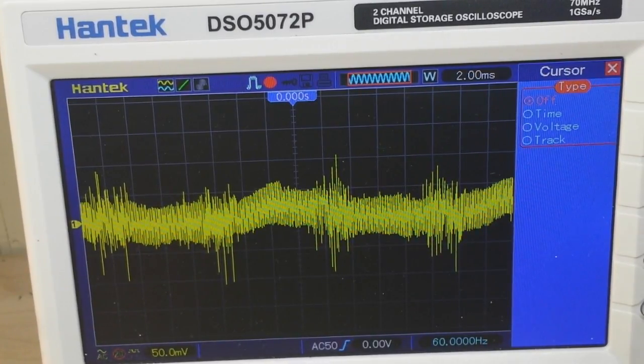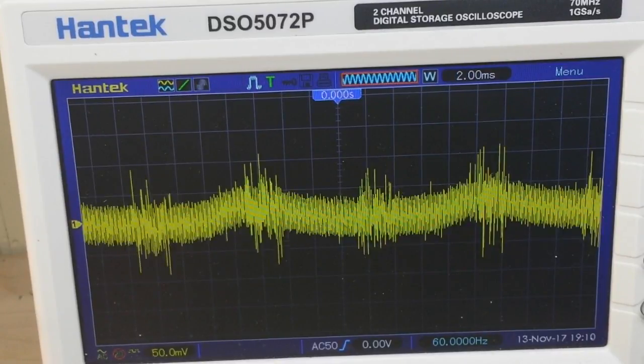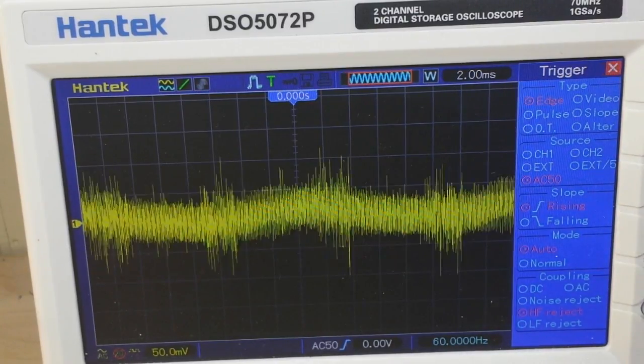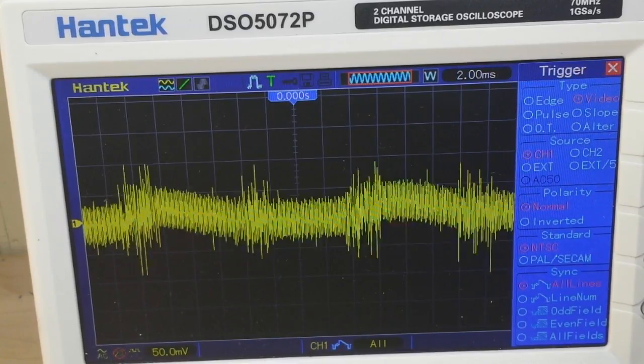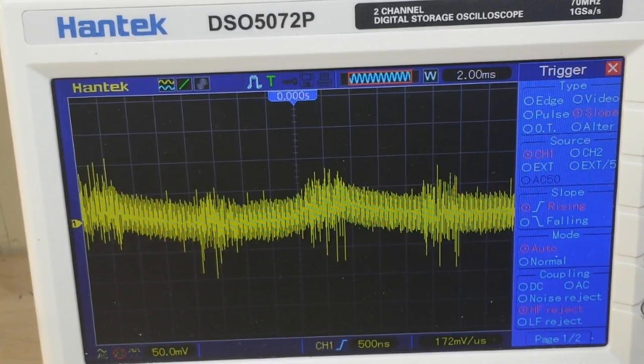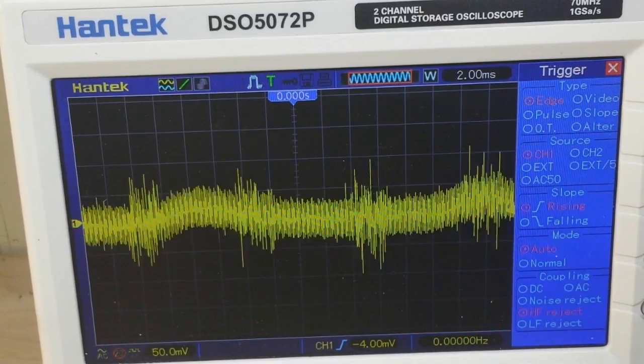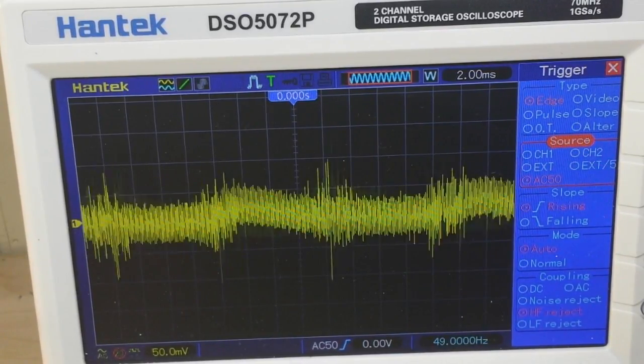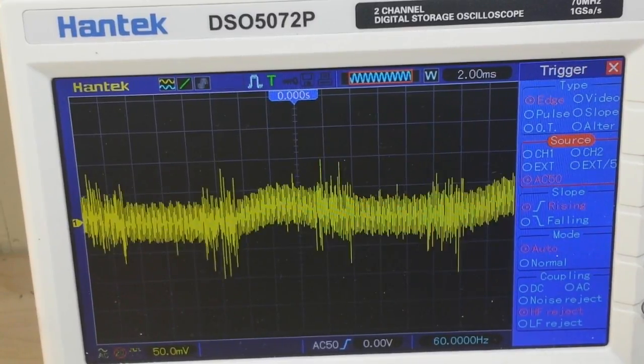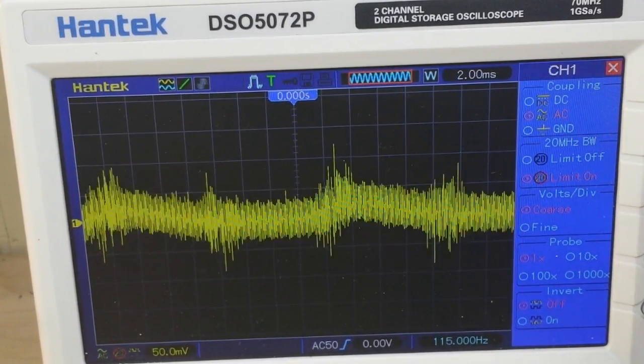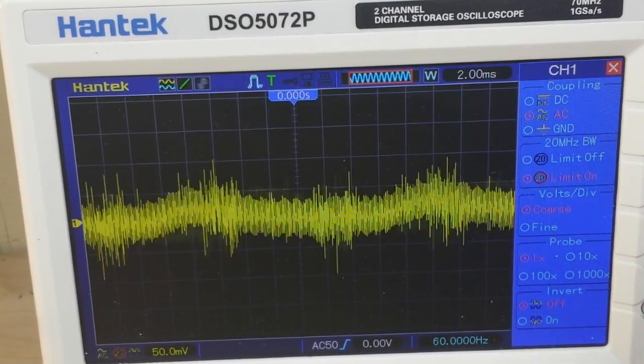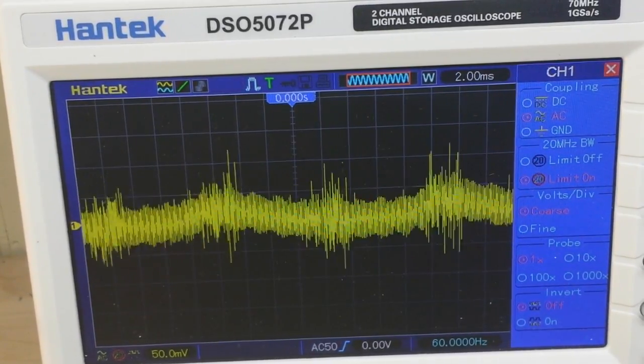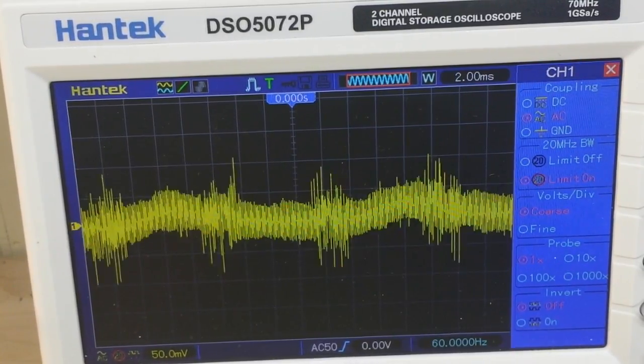All right, I'm going to turn off the cursors. We'll put it back in run mode. A couple things I want to show you. When we go into the trigger menu, one of the things we want to do here is adjust our trigger to our external. And then our channel, we definitely want to be AC coupled and we want our bandwidth limit on.